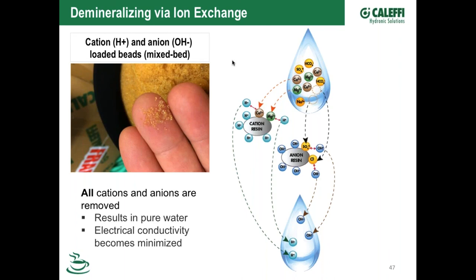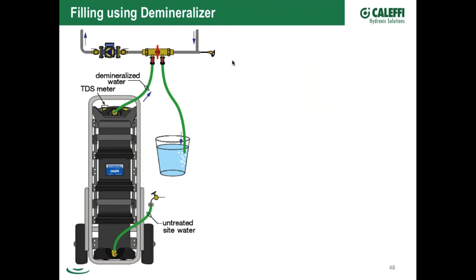All right, so this shows kind of how our cart works. If you have valves like this, you can put it in one side, have an isolation valve between the fill and the purge, and just leave it there until you check the TDS meter on top of our cart going in, and check the TDS of the water coming out the other side. When it gets to the same TDS, you know you've flushed all the old water out and it's completely filled with water that's gone through the hydro fill cart, with the TDS pulled down.